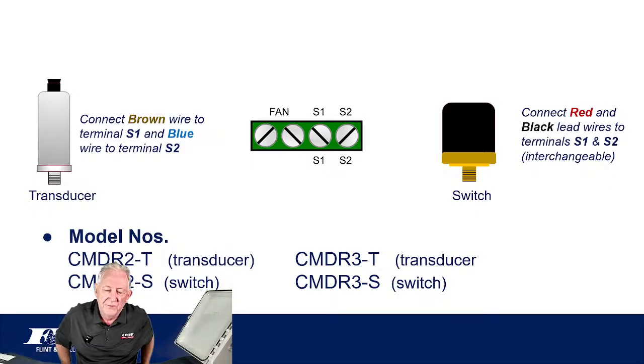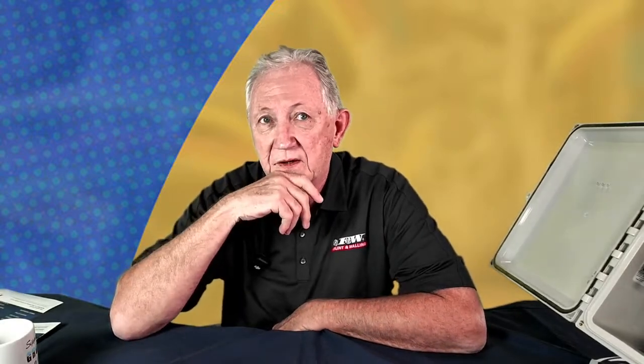If you're going to set whatever pressure you want to keep as your so-called constant pressure, and you've got a pressure switch, the black portion on the top side of that switch is like a rubber boot. You can pop that off, and there'll be a plastic tower inside with a hex nut in the center, like a standard conventional pressure switch. You go down on that nut with a nut driver and turn it clockwise to increase pressure, counterclockwise to decrease pressure.